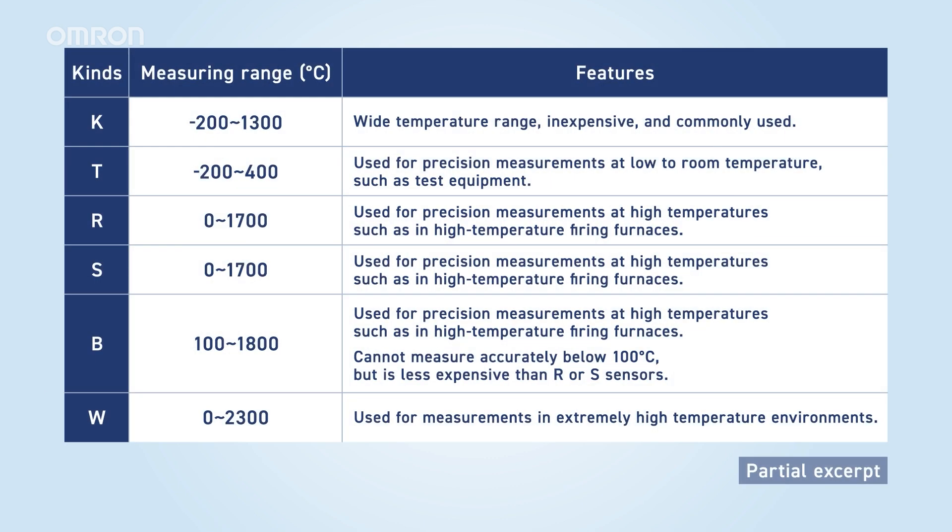Thermocouples vary by material and are chosen based on measurement range, accuracy, and environment. K-type thermocouples are popular for their wide range and low cost. T-type thermocouples are used for precise low-temperature measurements, while R, S, and B types are for high temperatures. W-type thermocouples are used for extremely high temperatures, around 2,000 degrees Celsius. Click here for the details about our temperature sensor.